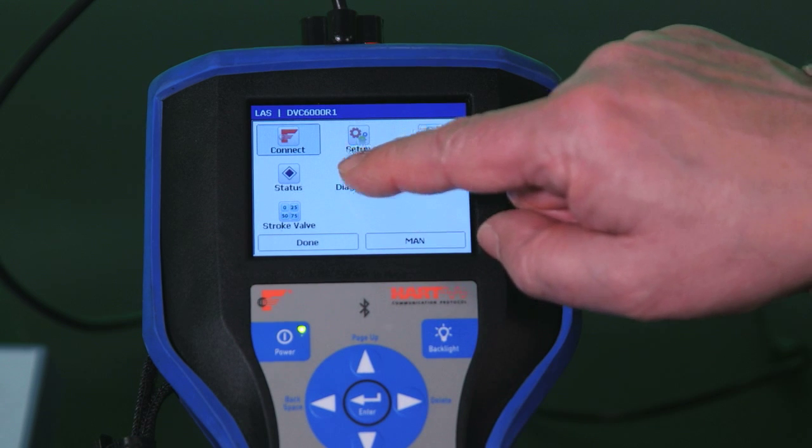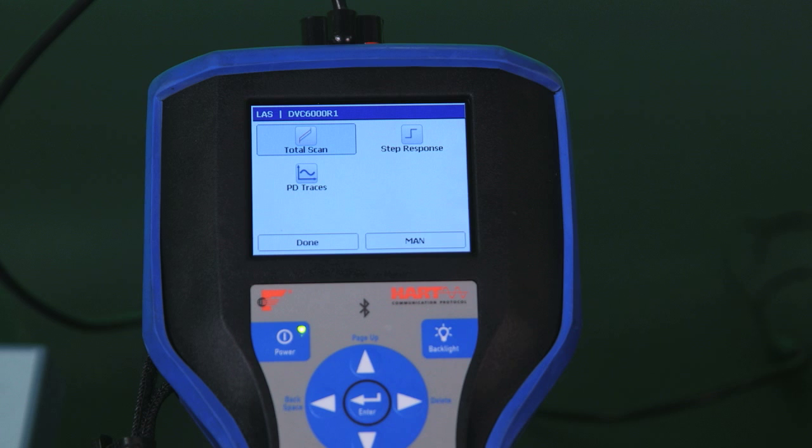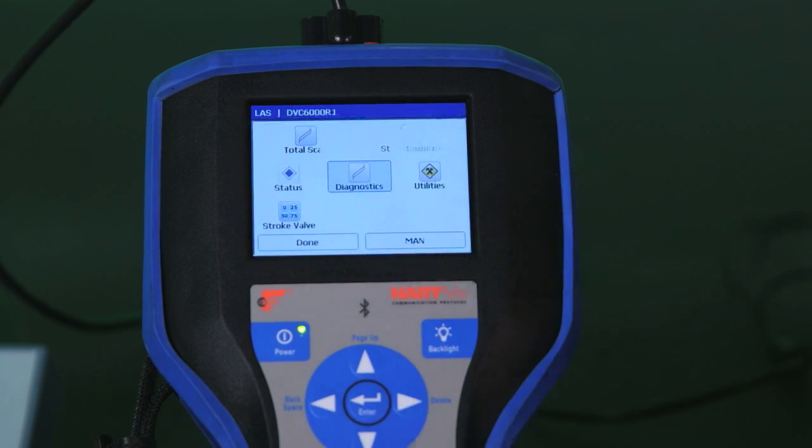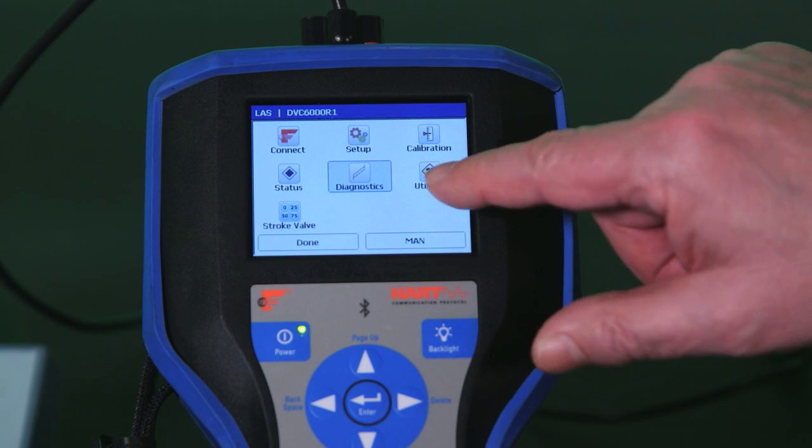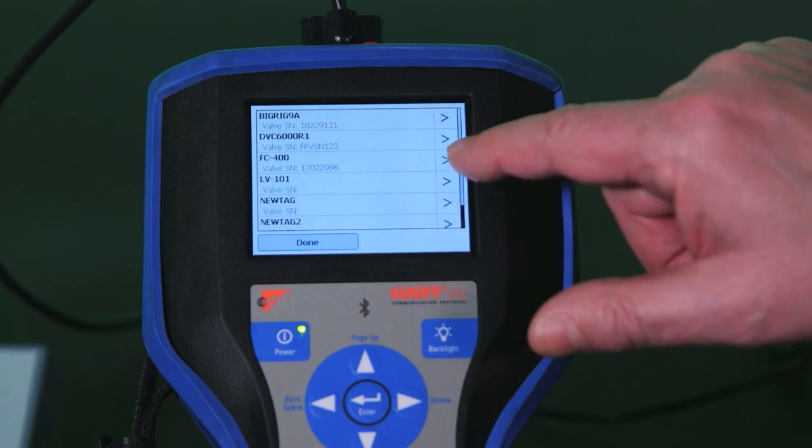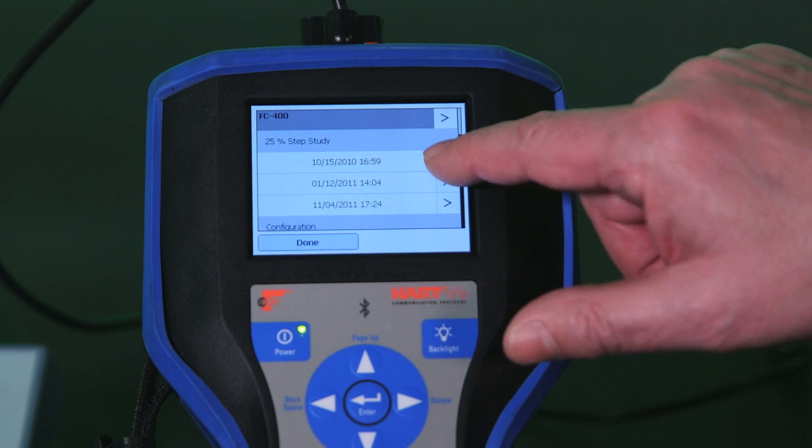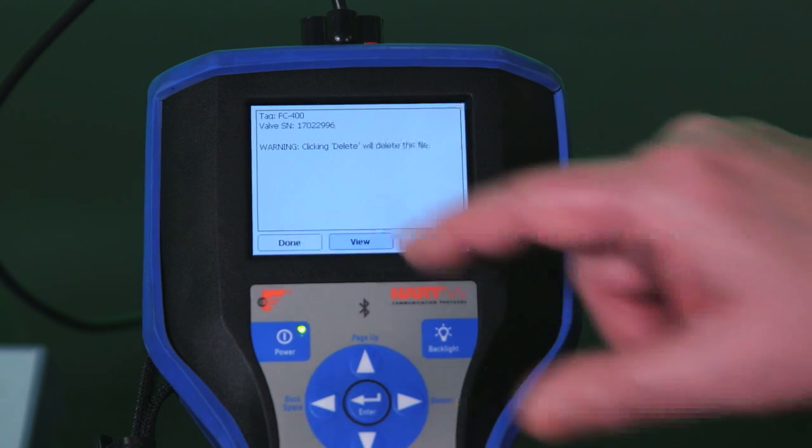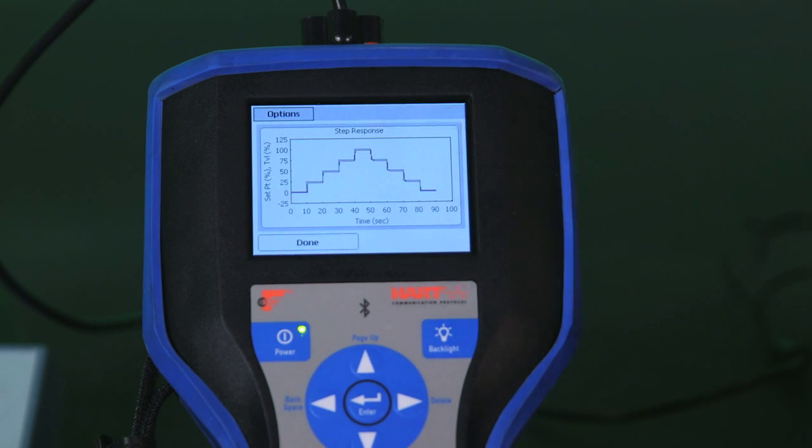I can now select the diagnostics that are available in valve link mobile. As you can see you can do things like a total scan for a valve signature. You can do a step response. For example if I select that one you see the step studies you can run. Because it takes some time to do those rather than run them right now I'm going to just show you the results of some that were run recently. So I'll call up some results on this one and you can see the type of results that are displayed in valve link mobile with these diagnostics.